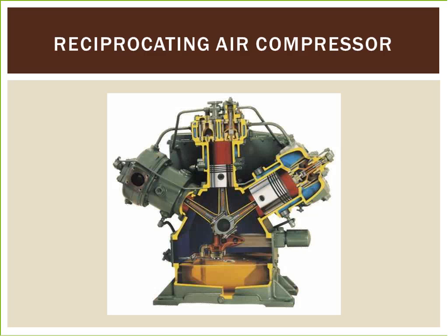Single-stage and two-stage reciprocating compressors are commercially available. Single-stage compressors are generally used for pressures in the range of 70 to 100 psi. Two-stage compressors are generally used for higher pressures in the range of 100 to 250 psi. Note that approximately 1 horsepower is equivalent to 4 CFM at 100 psi, and that 1 to 50 horsepower are typically for reciprocating units. Compressors 100 horsepower and above are typically rotary screw or centrifugal compressors.